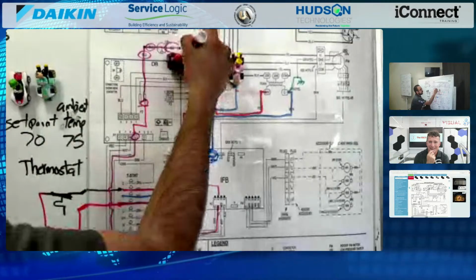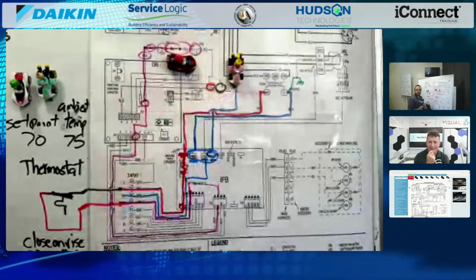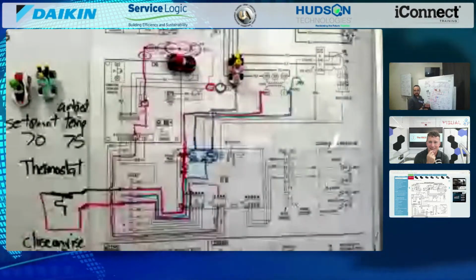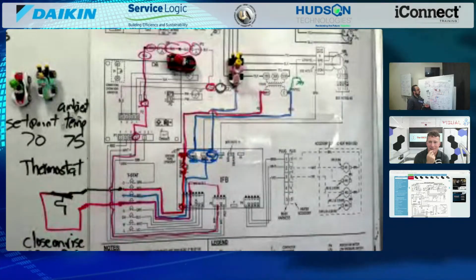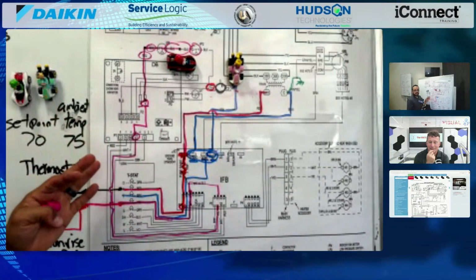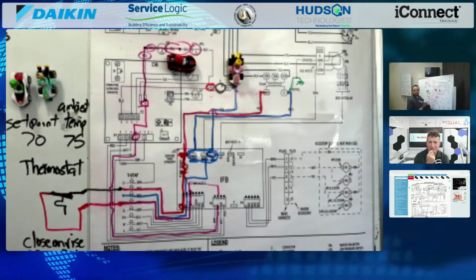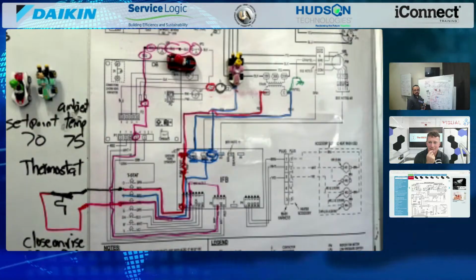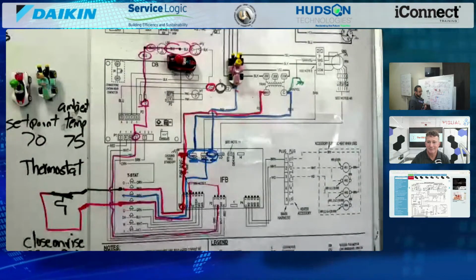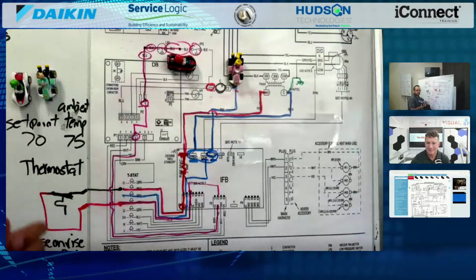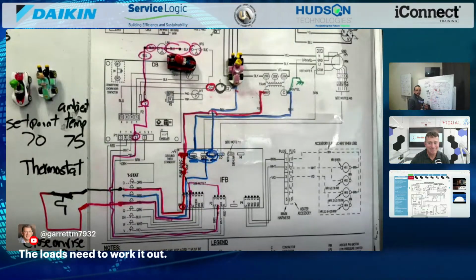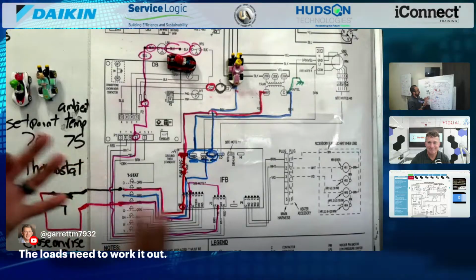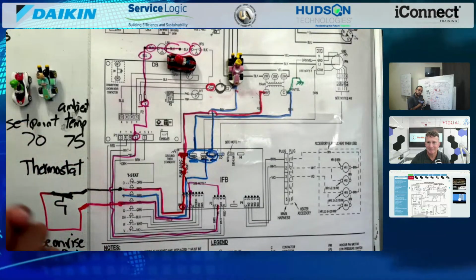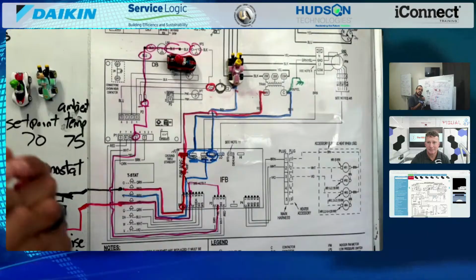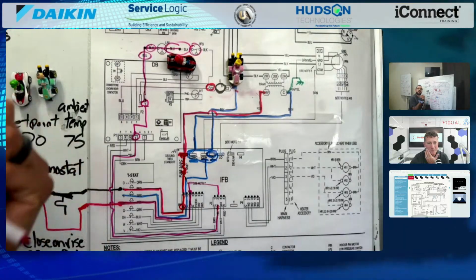This one is typically normally closed, but if you turn on your system and have a dirty condenser, it's going to open up. Typically the low pressure switch, if open, you don't even have to turn on the system because it's low on charge. The high pressure switch, if open, is usually when the system is on, because of higher pressure from a dirty condenser. But different things can happen to the pressure switches themselves. I tell the guys, don't change the pressure switches, they're a symptom of a bigger issue.